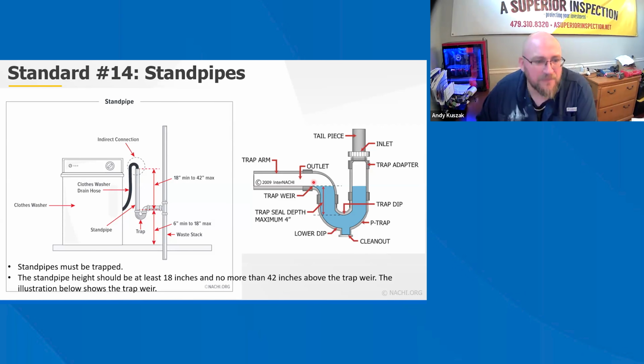Standpipes must be trapped. The standpipe height should be at least 18 inches and no more than 42 inches above the trap weir. The illustration shows the trap weir. So you can see the trap weir is here, right?